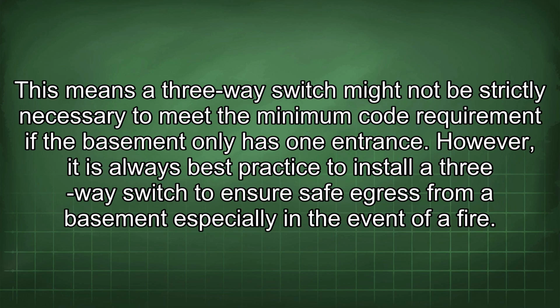This means a three-way switch might not be strictly necessary to meet the minimum code requirement if the basement only has one entrance. However, it is always best practice to install a three-way switch to ensure safe egress from a basement, especially in the event of a fire.